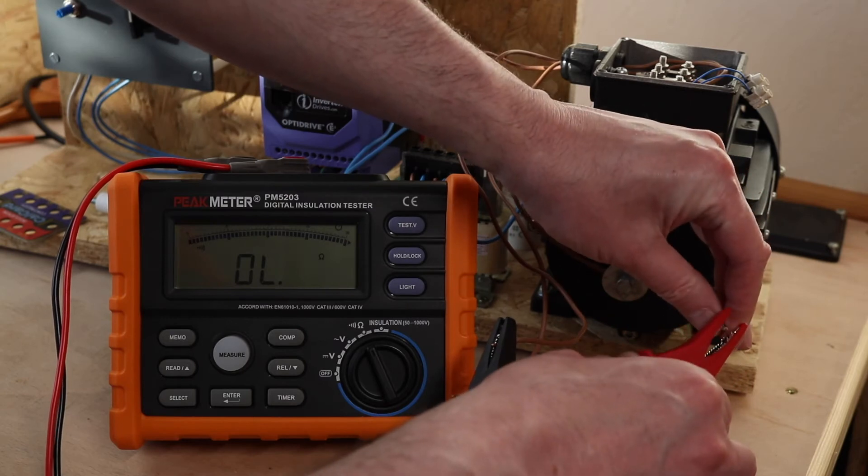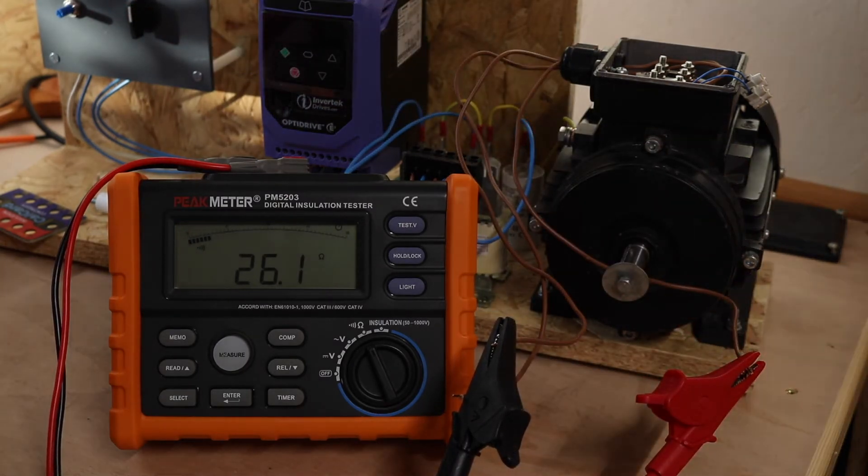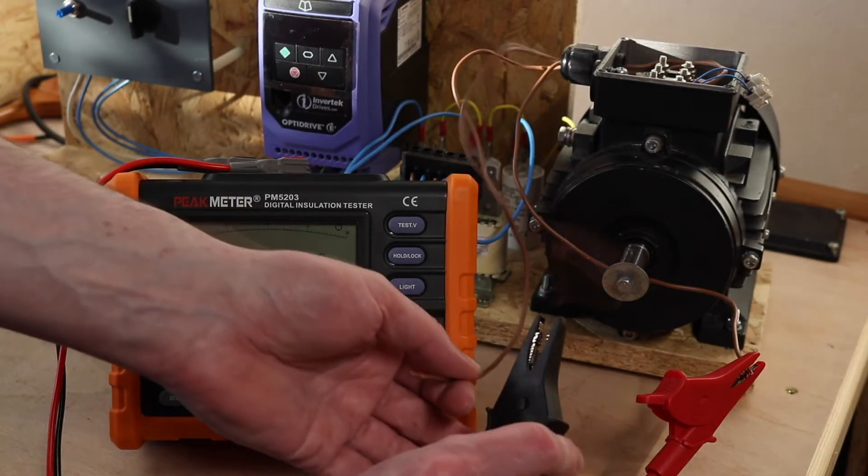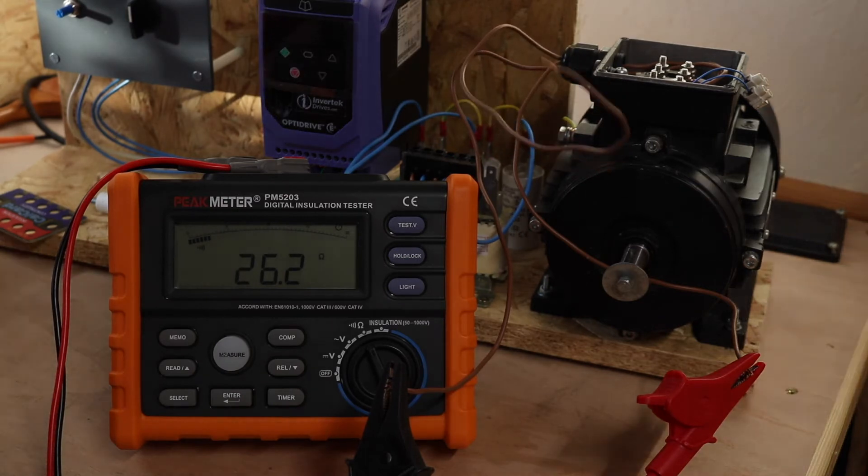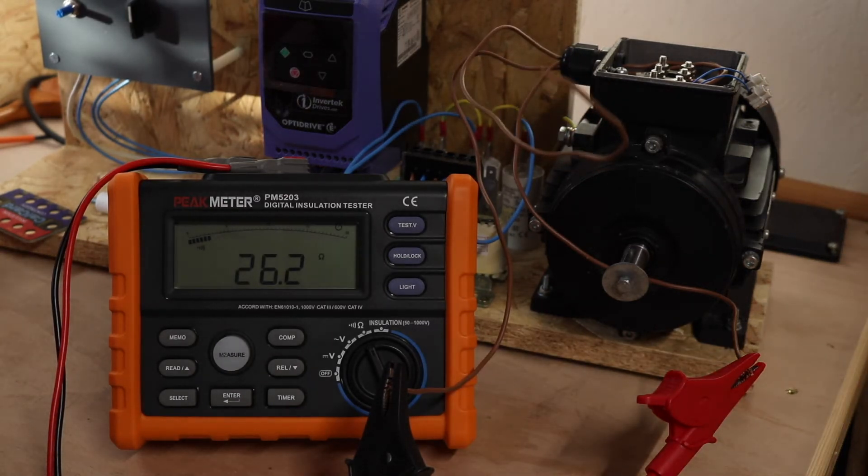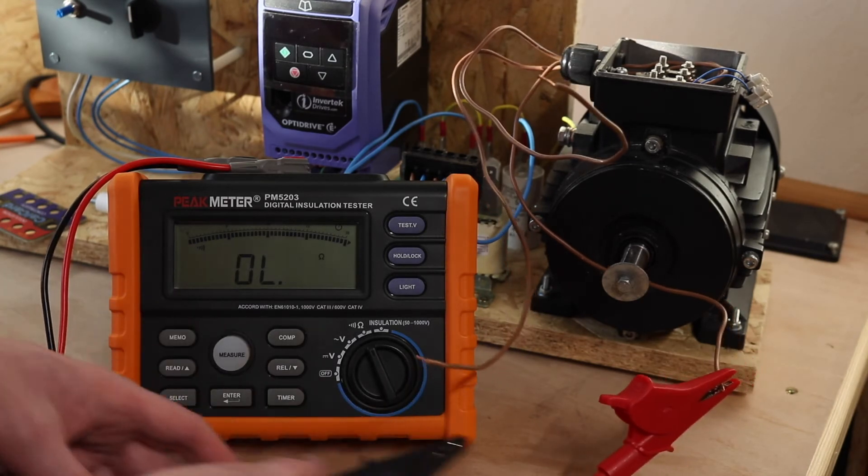Then go L2 to L3, 26.1 ohms, and then the final one, L3 back to L1 is 26.2. Okay, so that would be my first test.